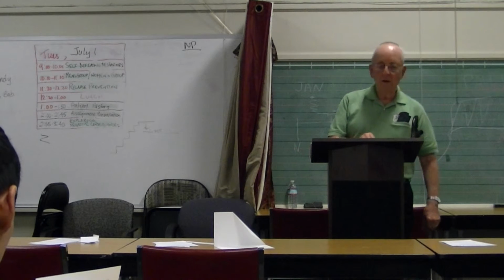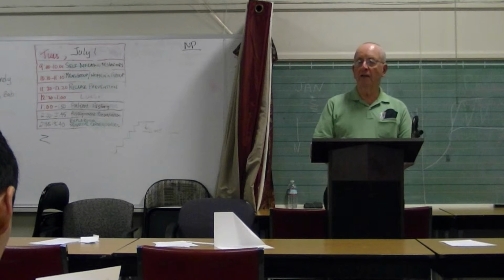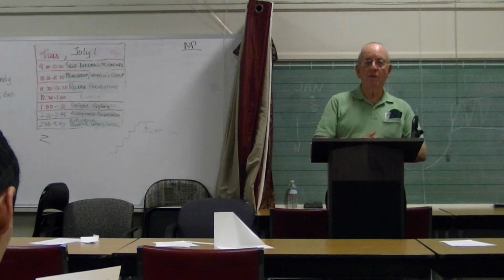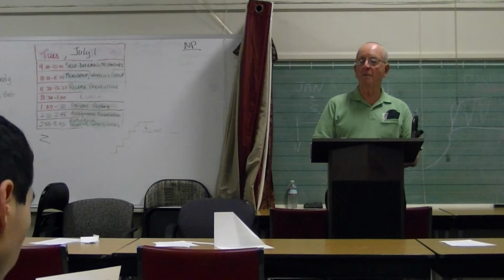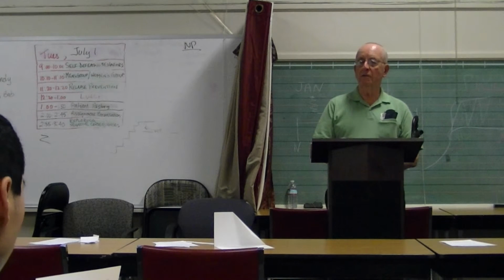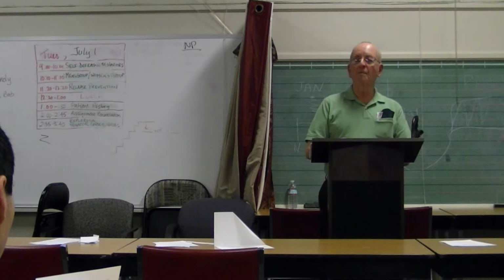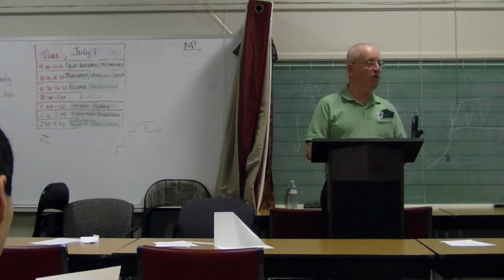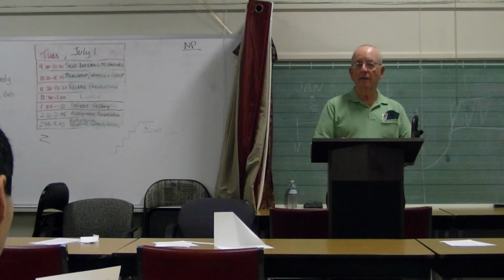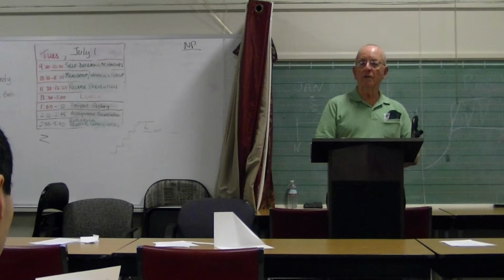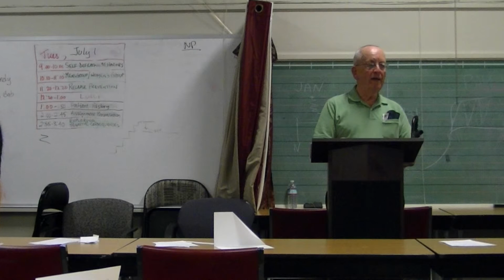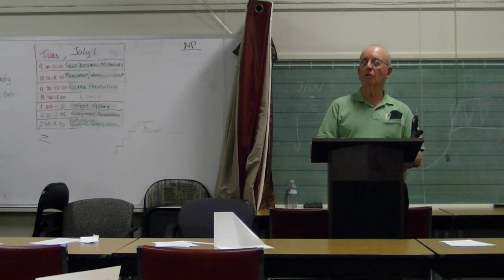The dispatcher, as he handles his daily loads, has a lot of decisions to make. The first equipment he uses are what they call base load machines. These are a series of generators which are the most efficient ones, and they're kept fully loaded, even to match your night loads. The other ones are called load following. They are added during the day, and these are set up with sensors so they will adjust themselves for load changes.